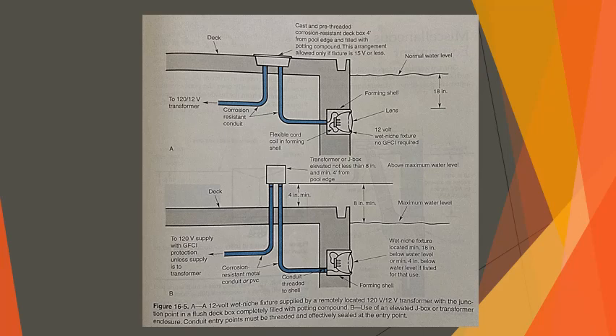The wet niche fixture is made up of a lamp within a housing, a flexible cord, and a sealed lens. The fixture assembly is enclosed in a metal shell called a forming shell, which is built into the pool wall. The flexible cord is long enough to allow the fixture, when removed from servicing, to extend out onto the pool deck. The wet niche fixtures are usually rated at several hundred watts with 12 volts of electricity from a weatherproof enclosed transformer.